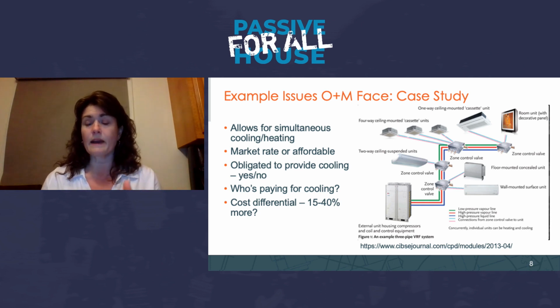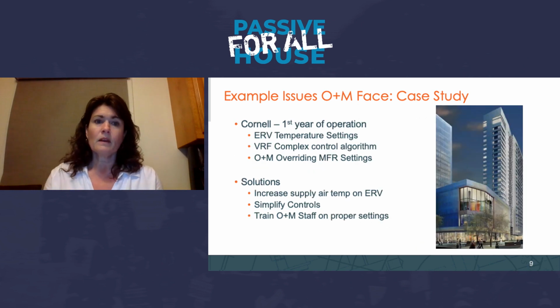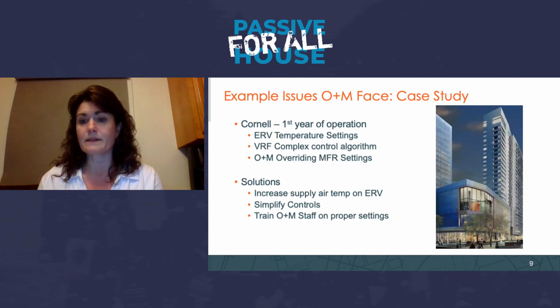But unfortunately, that extra loop can cost anywhere from 15 to 40% or more above a system that doesn't have that extra loop. And that's considered just a typical heat pump system, where the system is either in heating mode or cooling mode. You can't do both in the building. And so what we see in our affordable housing projects is a lot of the time that extra loop is value engineered out. So most of our affordable projects have either heating or cooling. Not all of them, but that's generally the case. So let's talk about what happens when that's the case.